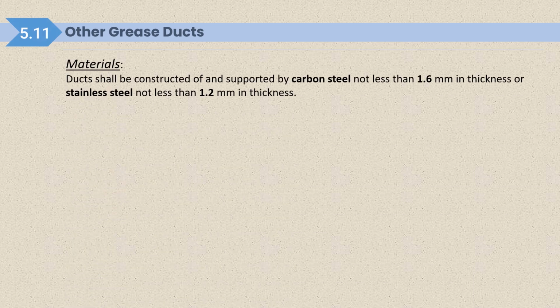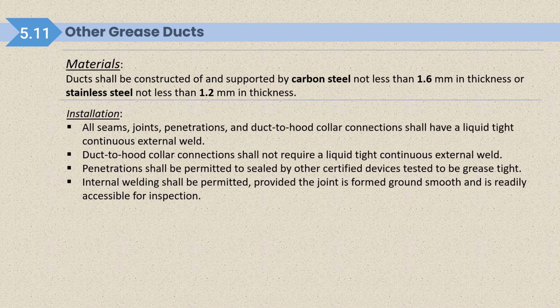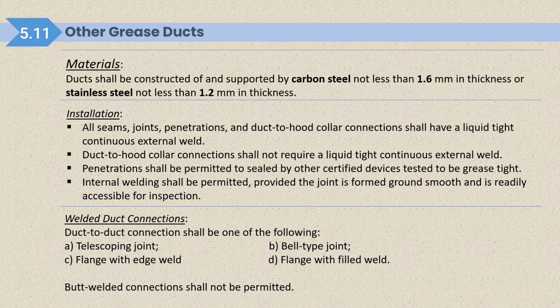For other grease duct material, ducts shall be constructed of and supported by carbon steel not less than 1.6 mm in thickness or stainless steel not less than 1.2 mm in thickness. Installation: all seams, joints, penetrations and duct to hood collar connections shall have a liquid tight continuous external weld. Duct to hood collar connections shall not require a liquid tight continuous external weld. Penetrations shall be permitted to be sealed by other certified devices tested to be grease tight. Internal welding shall be permitted provided the joint is formed, ground smooth and readily accessible for inspection.